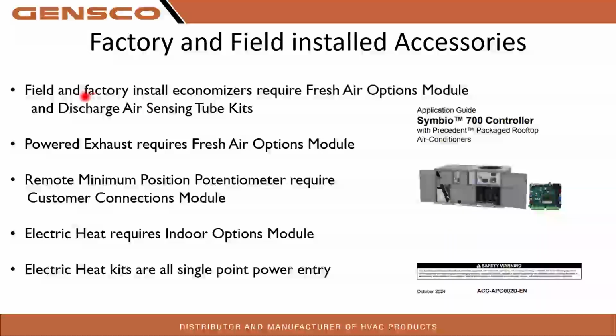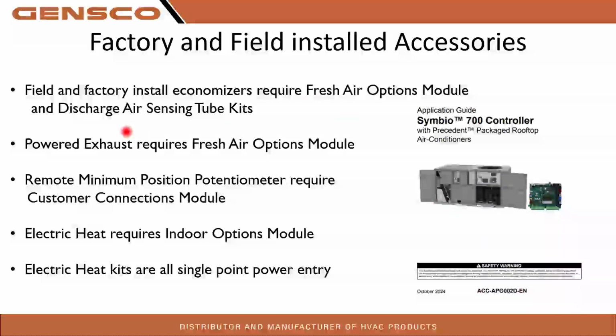If you order it from factory, you're going to get an economizer with the fresh air options module. I'm going to have a better picture of this, but the fresh air options module is going to sit inside the economizer right there. With the older economizers, you just had a mixed air sensor in the return air compartment and near the fresh air. This economizer, the Symbio economizer, uses the discharge air sensing tube kits. I'll show you that.